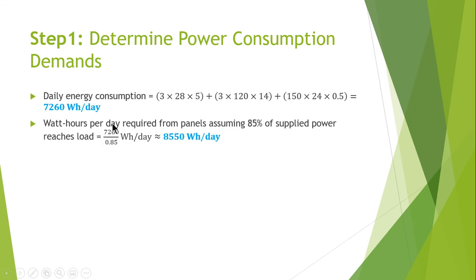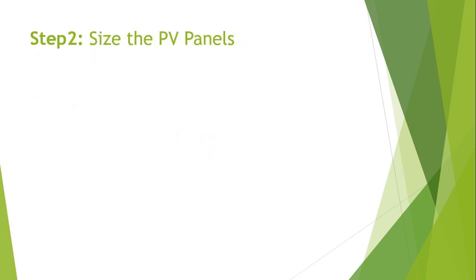The watt-hours per day required from the panel, assuming 85% of total supplied power reaches the load, is calculated by dividing the daily energy consumption by 0.85, giving us 8,550 watt-hours per day.